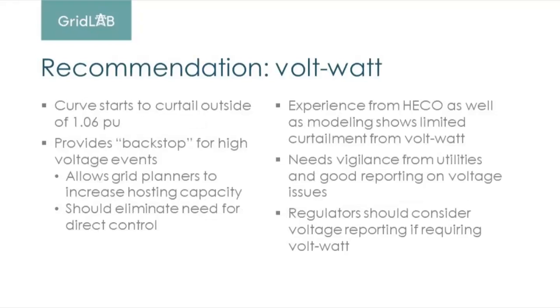And the second recommendation, volt-watt, is going to be a little bit more controversial, because it has some real concerns, especially from the developer and customer, about the potential impact of curtailment. But we really think that if you're going to implement volt-watt, you would only do real power curtailment after 1.06 per unit. So that's outside the ANSI range. You would be rarely doing this, right? You'd only be curtailing if the voltage gets outside of the ANSI range. That's pretty important because that doesn't happen very often, and utilities have an obligation to keep voltages on the distribution circuit within the ANSI range.